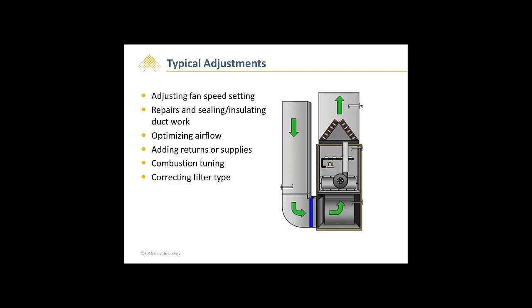So what do you do after you take those measurements? After you take the measurements, you'll be able to determine the pressure drop over the filter. You'll be able to determine total external static pressure as well as the pressure drop over the A coil. If the pressure drop over the filter is too high, this is a sign that the filter is too restrictive. The causes of this restriction could be a dirty filter, wrong filter type. Also, a pressure drop over the filter could also mean it's an issue with the return.